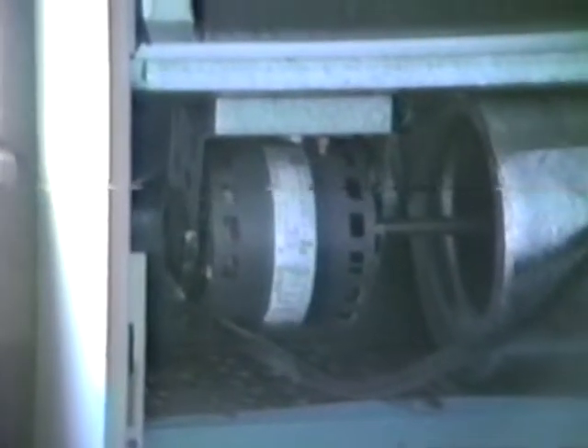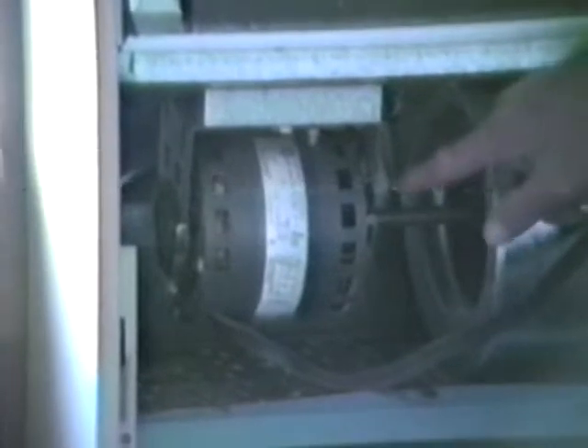Got a shot now of the fan motor. We talked the other day about our routine maintenance checks, oil in the fan motors. Right there, two oil entry ports. Also on the side over there, the little drain pan. It's obvious, of course, where that is and how to clean and inspect that.